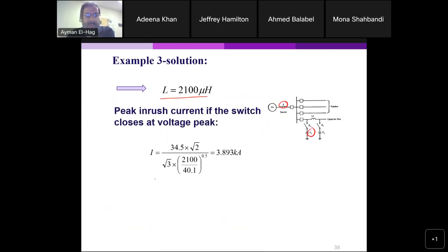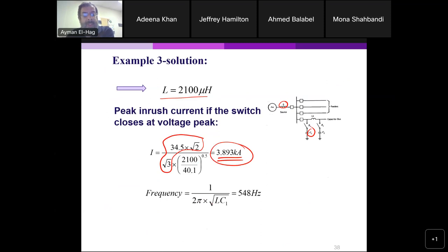So your I, the peak value of the current: we take the peak voltage, multiply by root 2, divide by root 3, and then divide it by the surge impedance, so you'll get a current equal to 3.893 kiloamps. That is your inrush current coming from the source supplying the capacitor. And the frequency, 1 over 2 pi root LC, is 548 Hz. So that is very, very similar to the previous example.